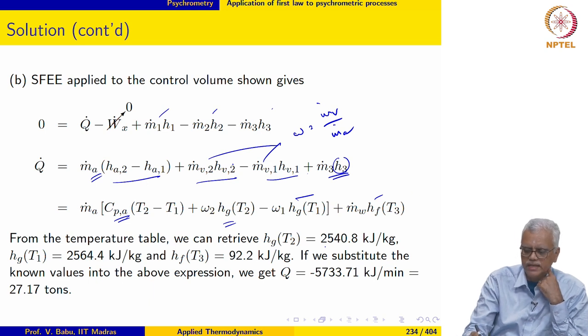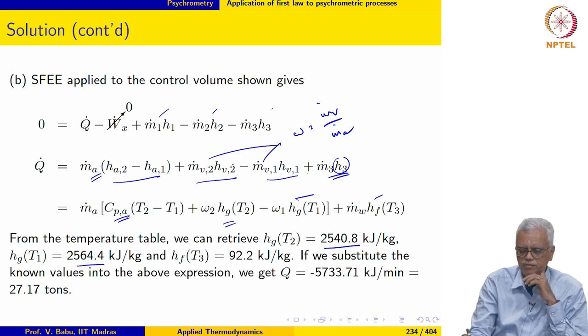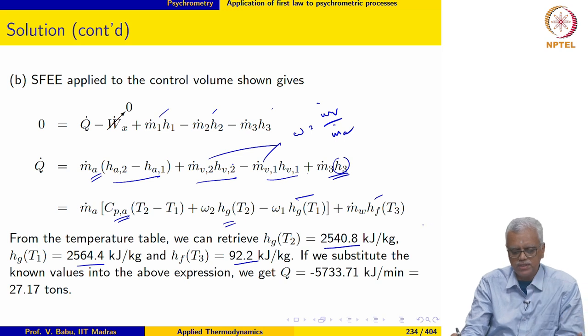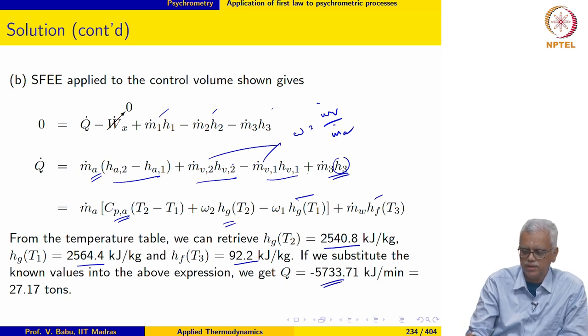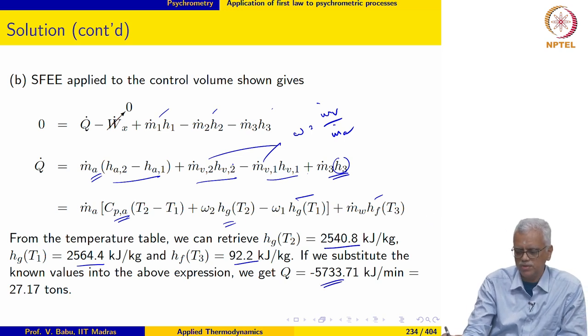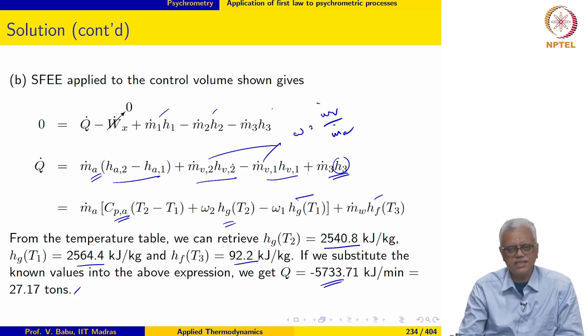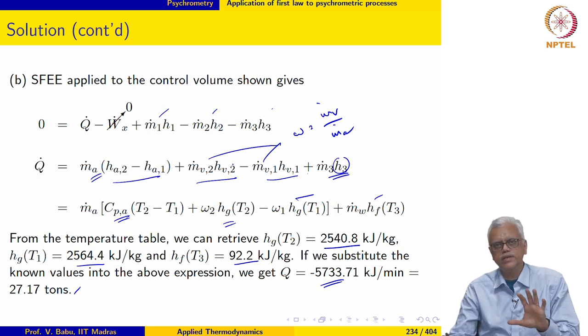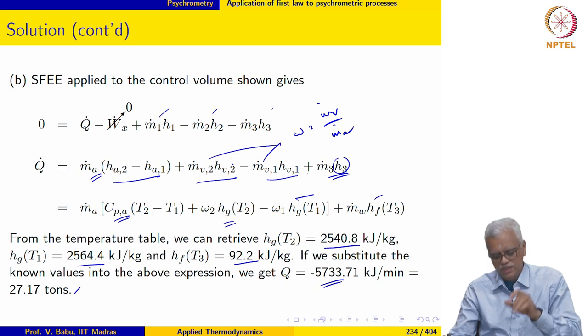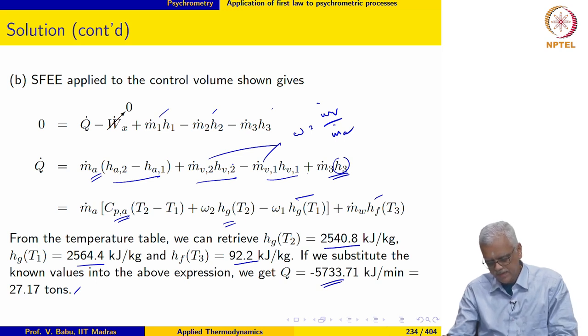Retrieving hg(T₂), hg(T₁), and hf(T₃) from the temperature table and substituting into the energy expression, the cooling capacity Q works out to 27.17 tons of refrigeration.